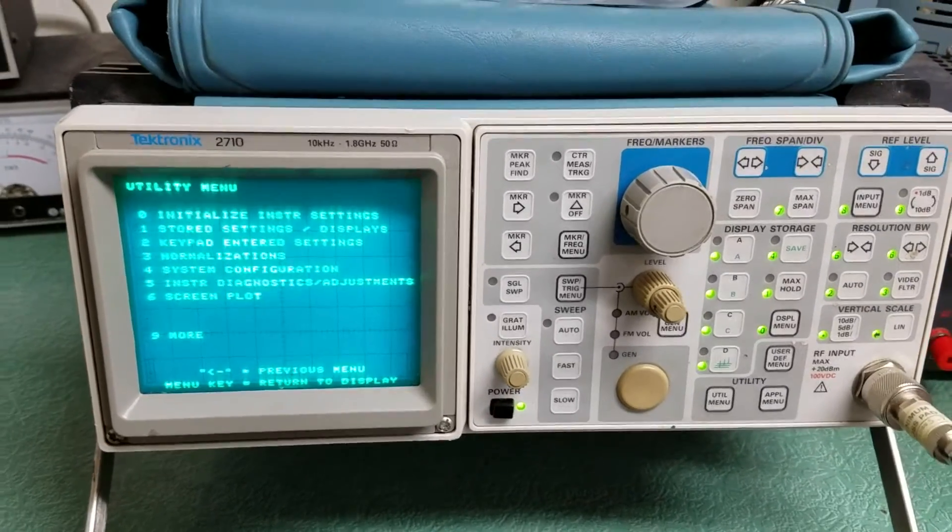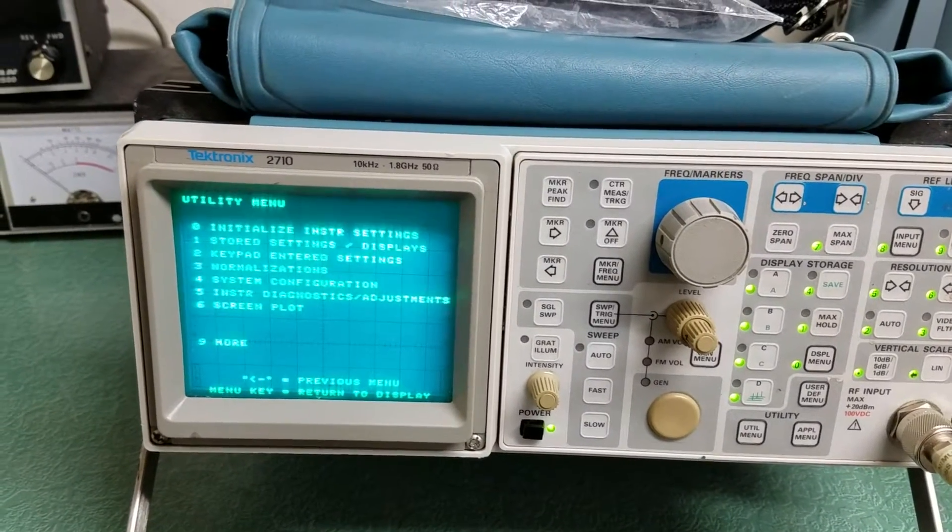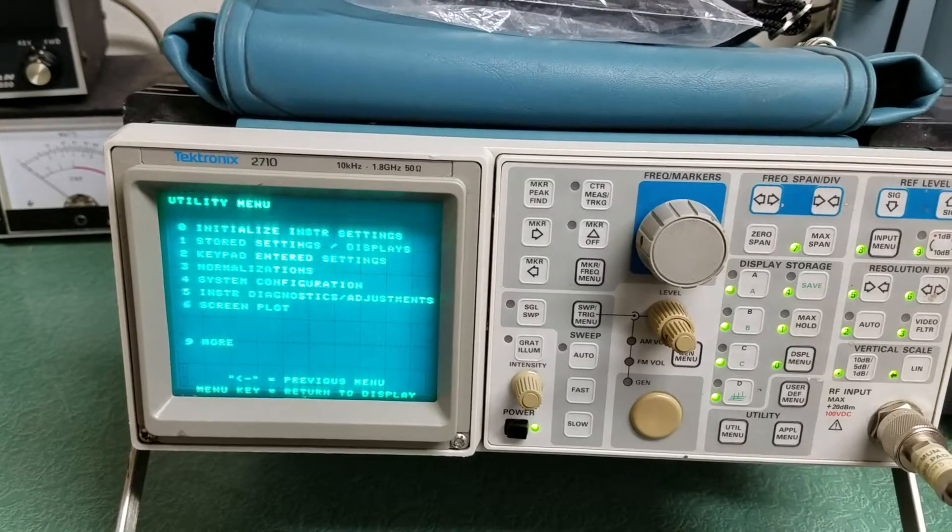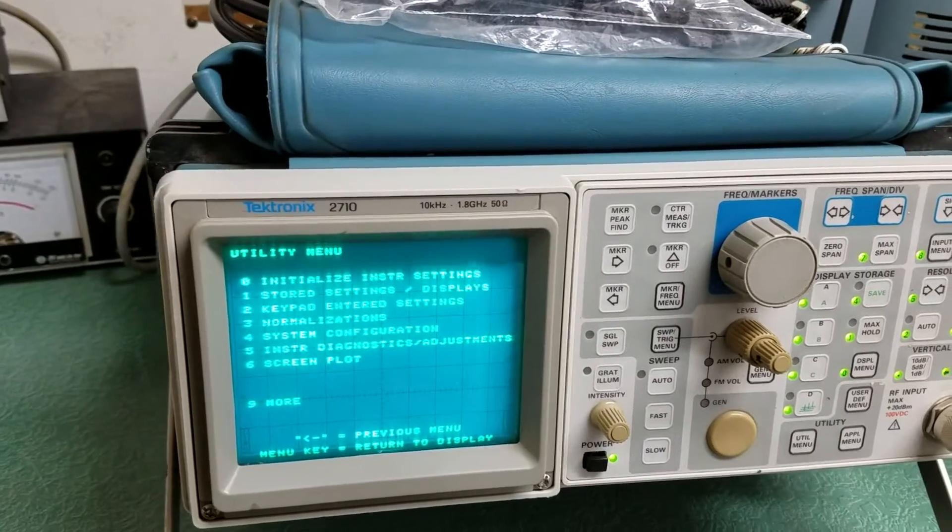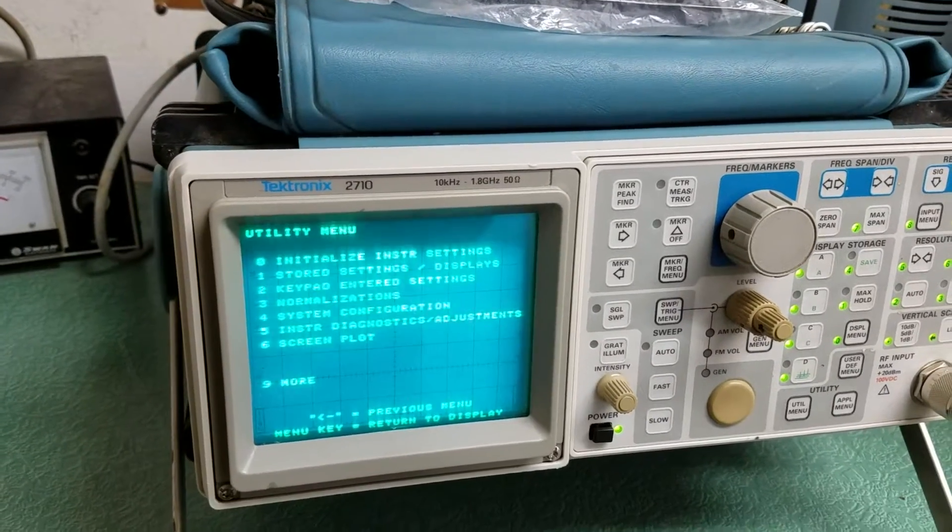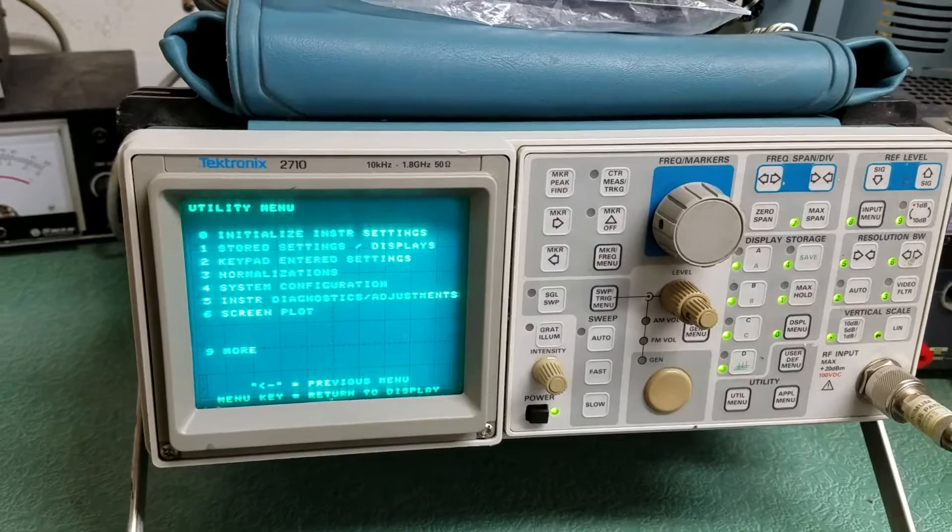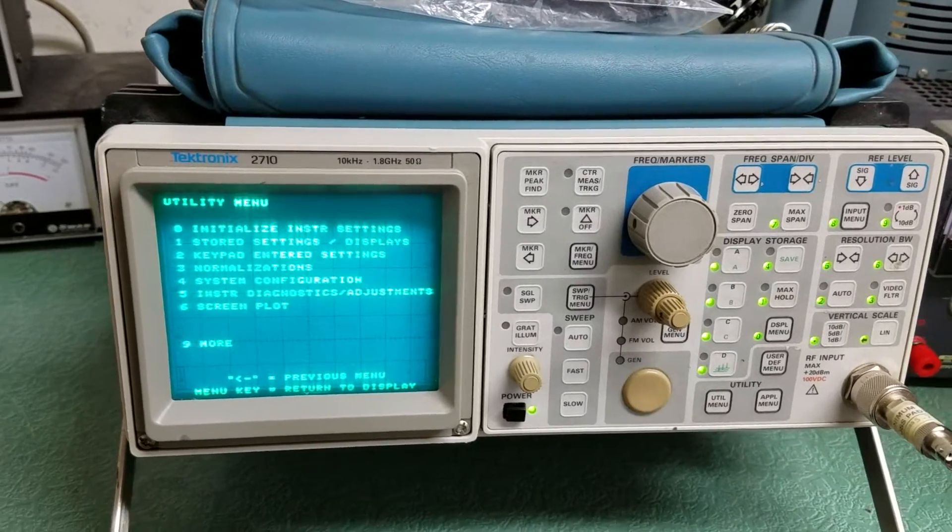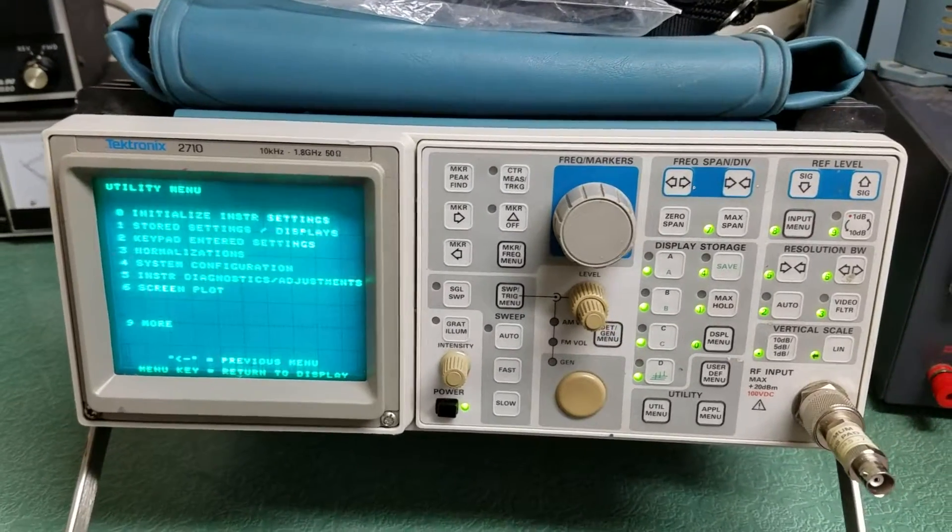So here is the Tektronix model 2710. This is a 10 kilohertz to 1.8 gigahertz 50 ohm spectrum analyzer, I believe what these are called.